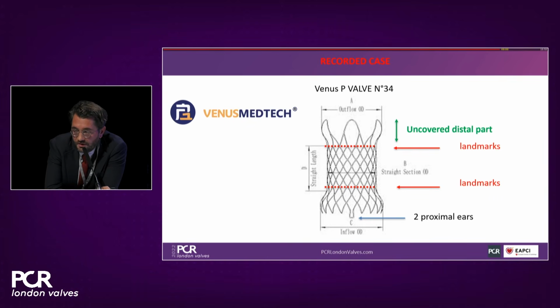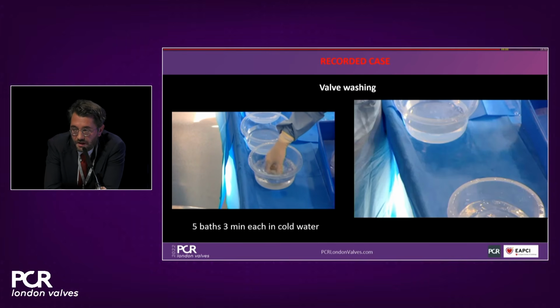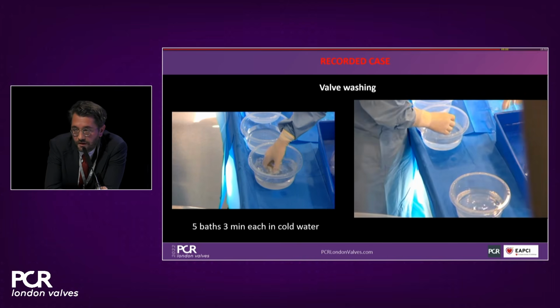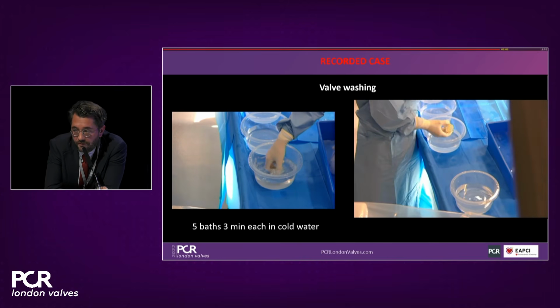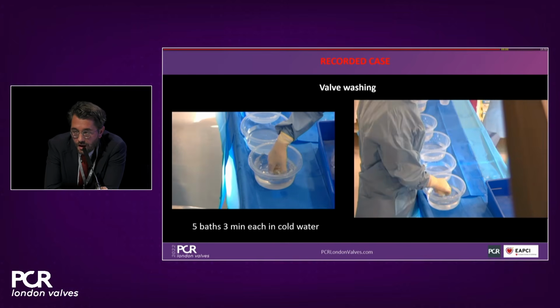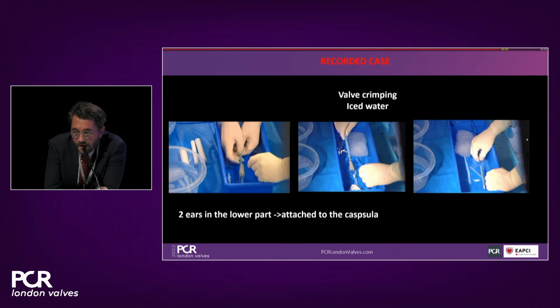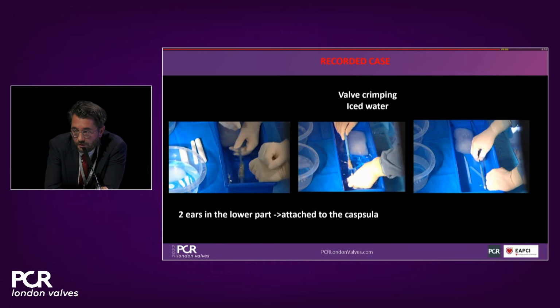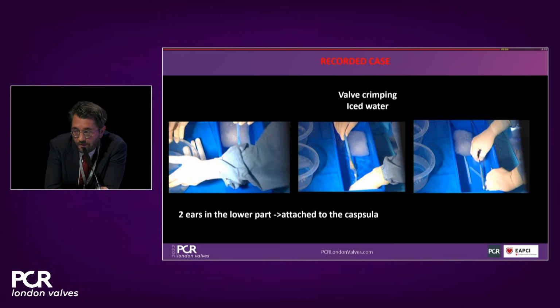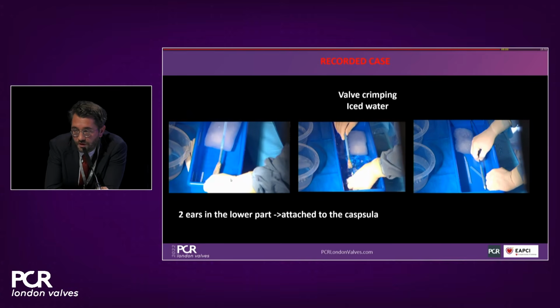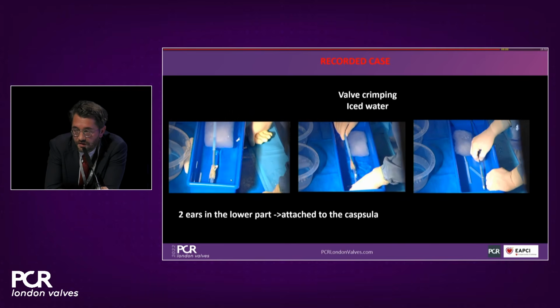And you can see in red that there is landmark on the valve that you can see on the angio. And you can see also that there is two proximal ears that will permit to fix the valve to the delivery system. So there is a big time for washing the valve in cold water. You need at least 5 baths, and in total more than 15 minutes. And then you will have to crimp the valve. It's not cold water, but iced water. You need ice to make the valve going inside the capsule after having attached the two ears in the capsule in the delivery system.